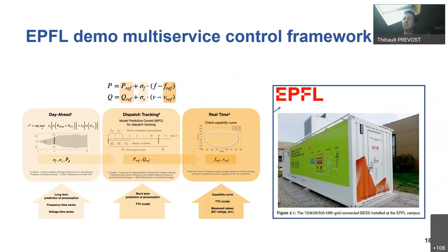Just an overview of what has been done in EPFL. They retrofitted an existing unit which was not designed to be operated in grid forming. So they added this constant VF mode. They tweaked it a bit to have it still operating in a kind of black start mode with this droop control, so a constant for the power plus droop, but in grid forming mode. The thing is that they can't operate like that forever. So they have a Modbus controller that updates all the references every 200 milliseconds.